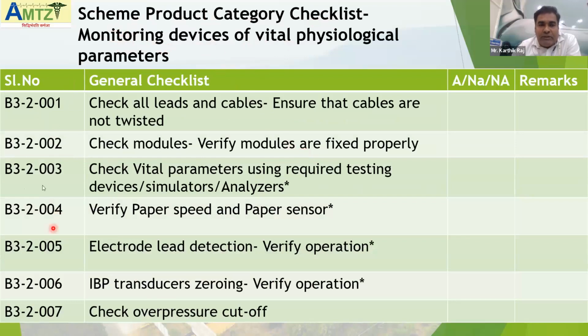Under that, you can see there are points. For example, the first point: check all the leads and cables, and ensure the cables are not twisted. It is about how you maintain the cables. If you take a patient monitoring system, more than 5 cables are associated. For ECG, monitoring the ECG waveform, there is one cable. SpO2 has another cable, temperature another cable. For NIBP, non-invasive blood pressure, you have a cuff with a tube that is connected. Respiration rate won't have a separate cable; it comes either from the ECG cable or from the temperature probe. Then you have EtCO2, end-tidal carbon dioxide, which has a cable. So we are making sure that all the cables are in good condition.